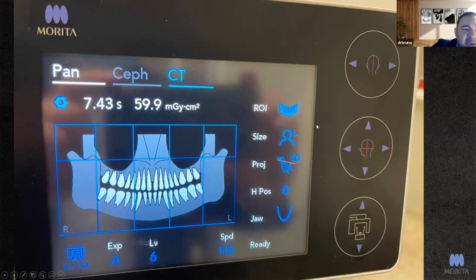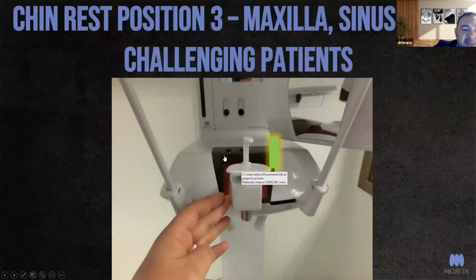Another important thing for you to think about whenever you're doing your panos, particularly if you have an X800, is your level. I don't know if you guys are using different levels for your panos. I like to keep my panoramic images with the X800s at level 6 and level 5. Those are the best ones. I think by default the unit comes at about 2. So if you are working with an imaging center and you want better image quality, please make sure your level is a 6. If you are using an X700, this previous unit here, please make sure that on your unit your level is a 4. That's the maximum we'll go here.